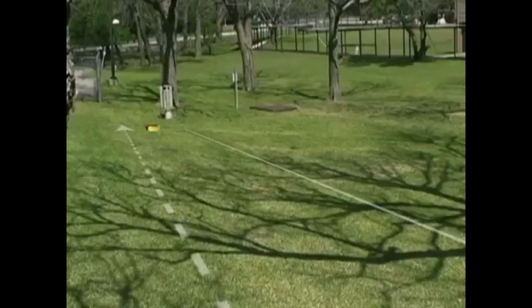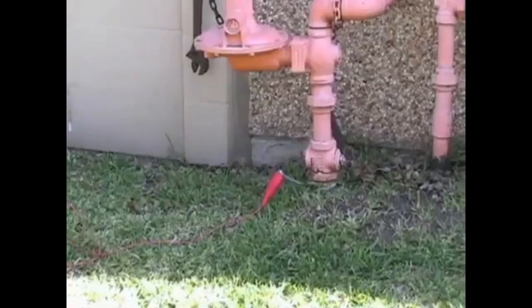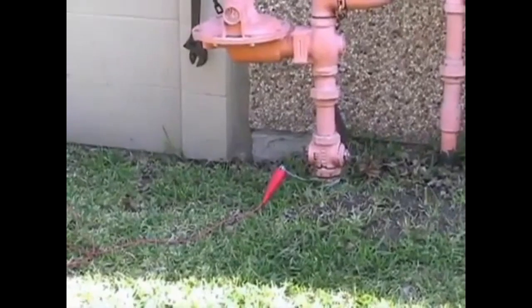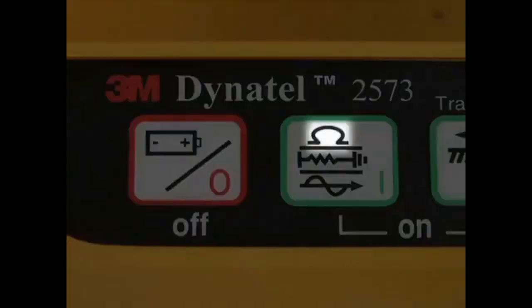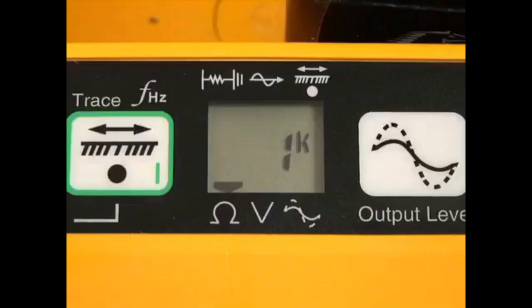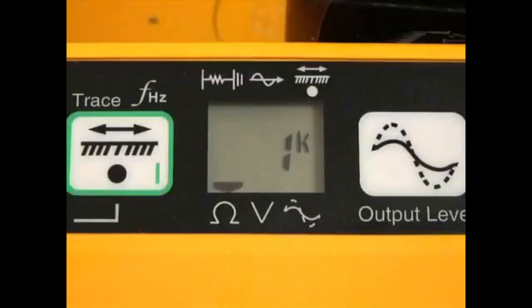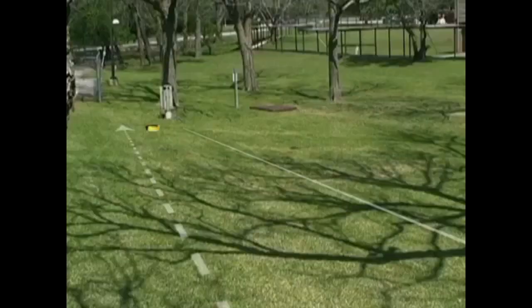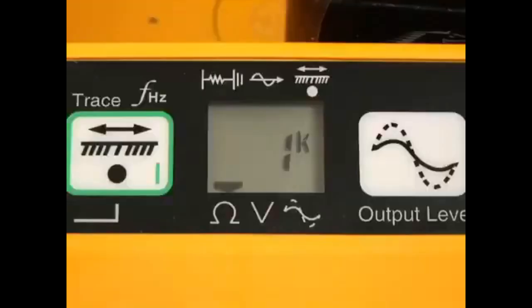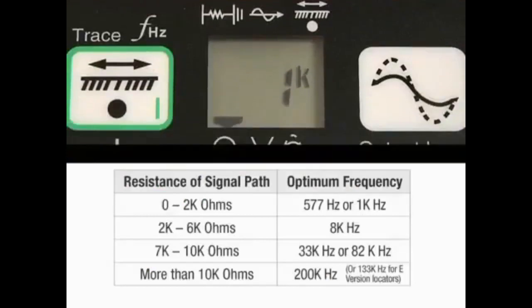Using the direct connect method allows you to determine the quality of the signal path circuit. This information can help you choose the best frequency to apply to the target conductor. Connect the transmitter to the target conductor and measure the quality of the signal path circuit by pressing the OHM key on the transmitter. A flag will appear in the lower left side of the display, indicating that the transmitter is in ohms mode. The resistance of the tracing circuit will be displayed. Based on the quality or resistance of the signal path, you can choose the optimum frequency for your application, using a reference chart.